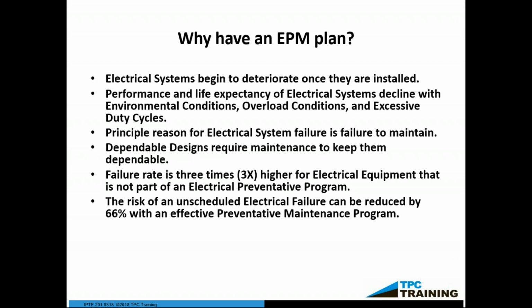Electrical systems begin to deteriorate once they're installed. Performance and life expectancy of electrical equipment and systems decline because of environmental conditions, overload conditions, or excessive duty cycles. The principal reason for electrical system failure is a failure to maintain. Dependable designs require maintenance to keep them dependable. Failure rate is 3 times higher for electrical equipment that is not part of an electrical preventive program, and the risk of unscheduled electrical failure can be reduced by 66% with an effective PME.